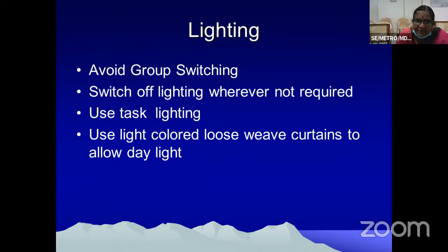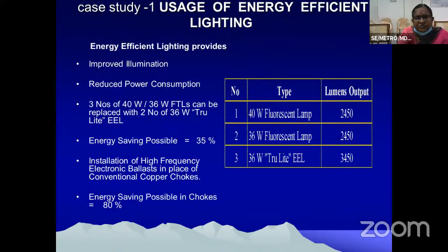Use task lighting. This they can use in many of the hotels and conference halls by using the occupancy sensors. Where lighting is required, it will be on. In other areas, it will be automatically off. Use light colored loose weave curtains to allow daylighting. So usage of energy efficient lighting gives improved illumination and reduced power consumption. 3 numbers of 40 watts or 36 watts fluorescent tube lights can be replaced with 2 numbers of 36 watts energy efficient lamps. Energy saving possible is around 35%.